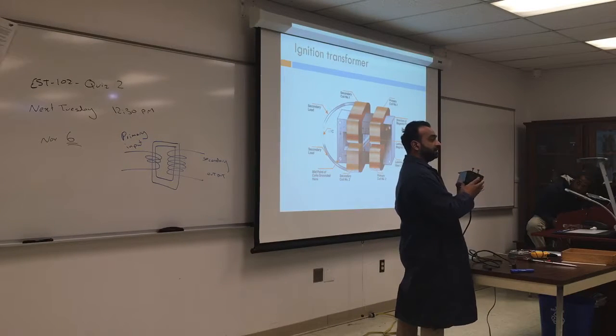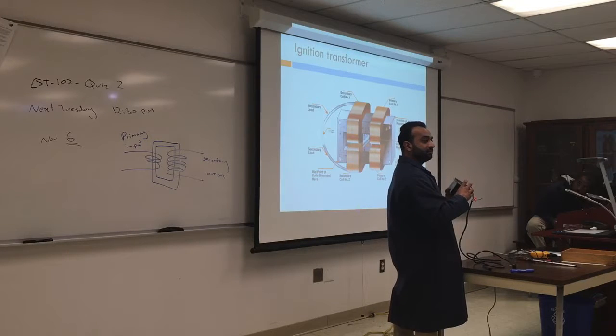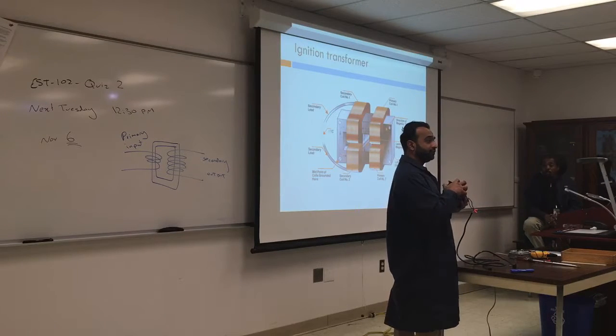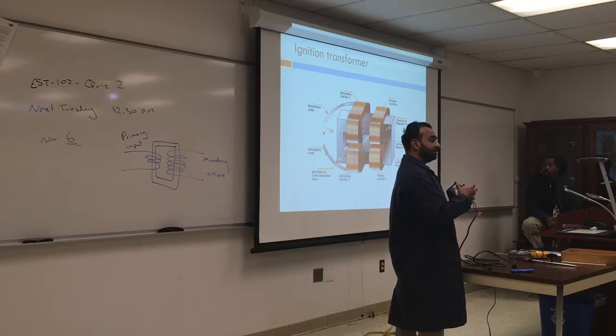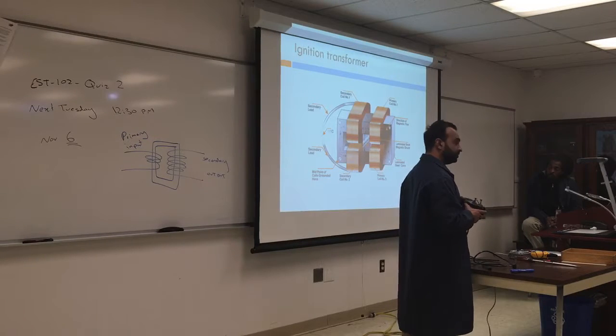These two are the leads. They have springs on them. Why? Because you want to ensure a solid connection between the transformer and the leads we saw before for the bus bar. They're supposed to have really good connection. If it's tilted, it's not touching, it's not going to connect properly. Instead of 10,000, you will get 9,000, 8,000.